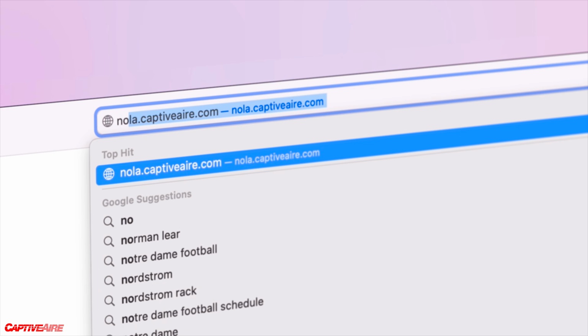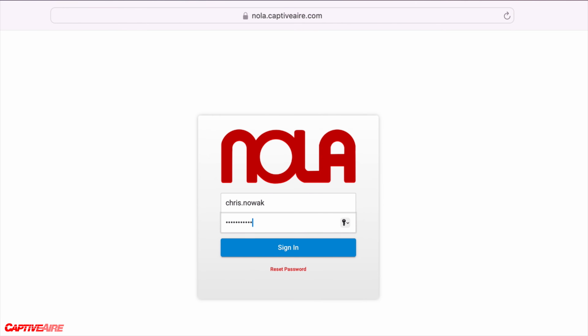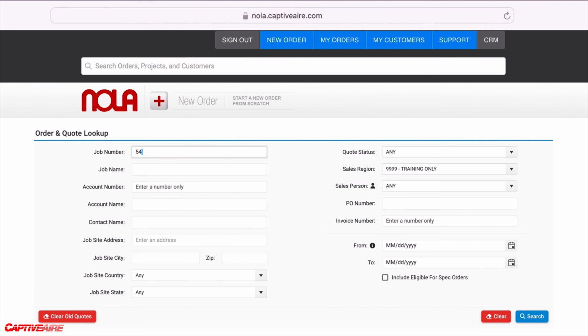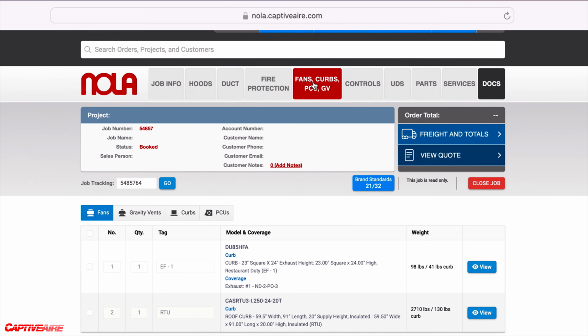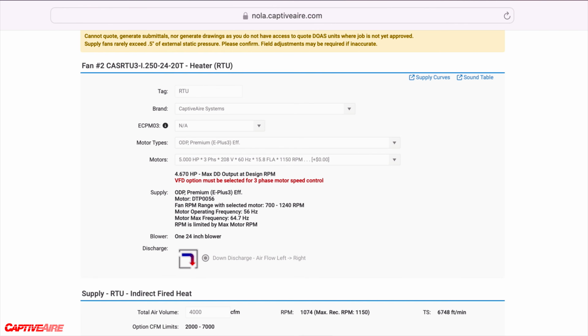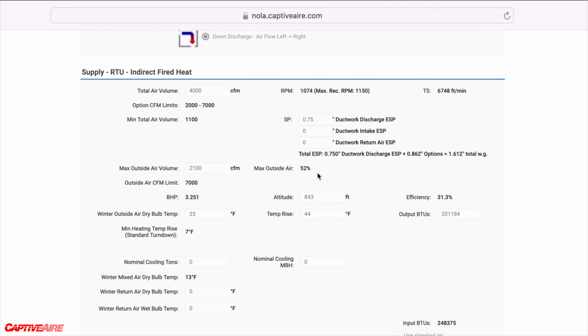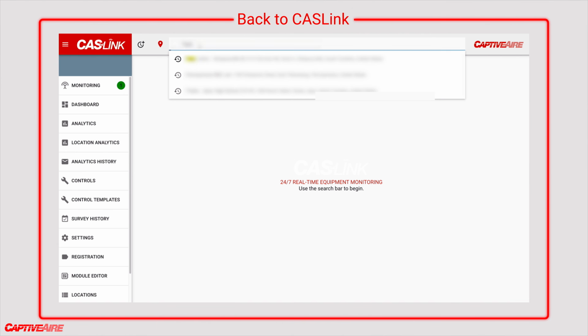The first thing he'll do is use NOLA, our internal specifying and quoting software, to find out a little more about the setup and intended operation of the unit in this particular building. It's serving as the primary space comfort for heating and cooling for this space, but also serving as the makeup air for the hood. So this unit runs at around 50% outside air. It's going to be interlocked with the hood system, and when it's on, it's running that 50% outside air versus when the hoods are off, it's going to be running full recirc air. Constant volume, no modulation. So it should be pretty straightforward in trying to review how the system's meant to operate.